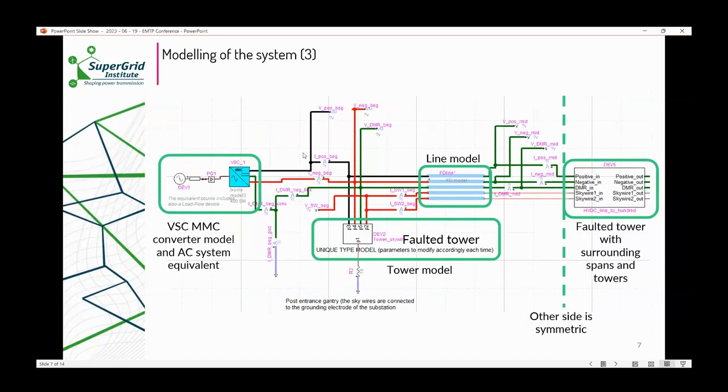So if you zoom out, what I presented is in this box on the right-hand side, which says faulted tower with surrounding spans and towers. Then if you neglect all these scopes, we have a FD line model on the left, which is, for example, 150 kilometers if you want to simulate the fault at the middle of the line. On the left, we have the line termination tower, and then we have the VSC MMC model with AC system equivalent. If you want to change the location of the fault along the line, other side is symmetric. We have the tower model and surrounding spans in the middle. On each side, we have an FD line, and we just change the length of this line. So if you want the fault to be 50 kilometers from the beginning, we put the left FD line model to 50 kilometers and the right-hand side FD line model to 100 kilometers.